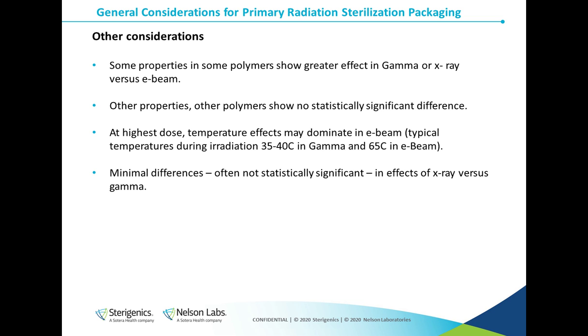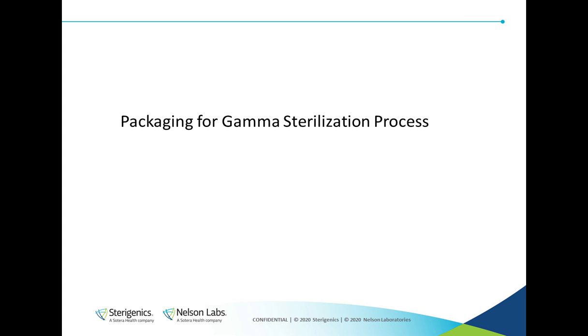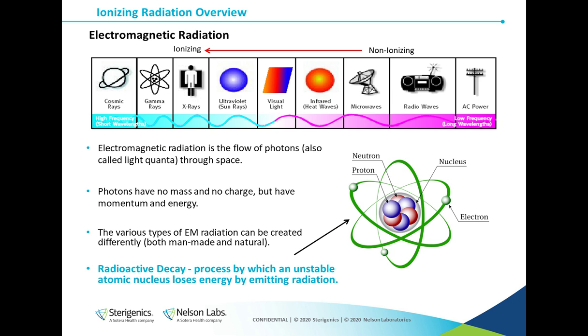At the highest dose, temperature effects may be more prevalent in E-beam versus gamma or X-ray. Typical temperatures in gamma and X-ray are a maximum of 35 or perhaps 40 degrees Celsius, whereas the maximum temperature might typically reach up to 65 degrees Celsius in electron beam. So if your product or packaging is impacted by temperature, this should be considered. And in general, there is typically little difference in material effects between gamma and X-ray radiation. Next, we are going to go over the packaging considerations for the gamma sterilization process. We will focus on the secondary packaging, or the shipping containers, and how this can impact the process.